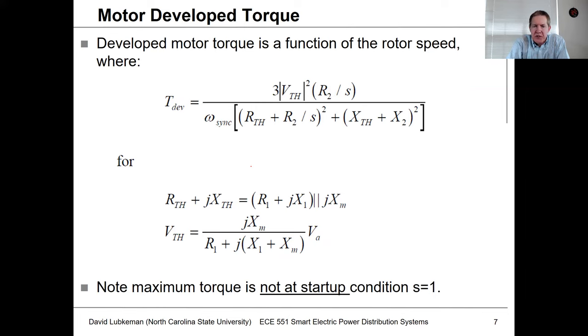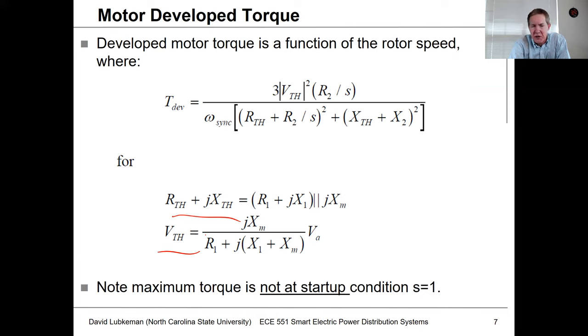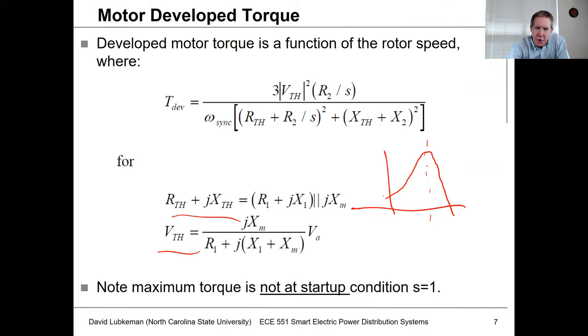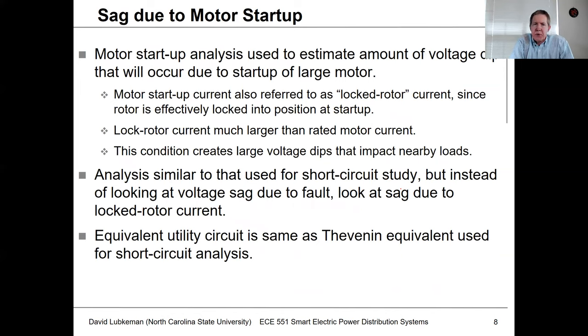These are the equations for the developed torque, which is a function of some Thevenin equivalent resistance and voltage for the machine. It's not really important to know this because at this point we're not doing torque-speed calculations. But if you look at this curve relationship, we get a relationship between the speed of the machine and the torque. At slip 0.03 we're somewhere around maximum torque, but when we start this machine up, the torque is not at maximum by any means — which is why these machines can stay in a low-speed condition until the rotor finally accelerates.